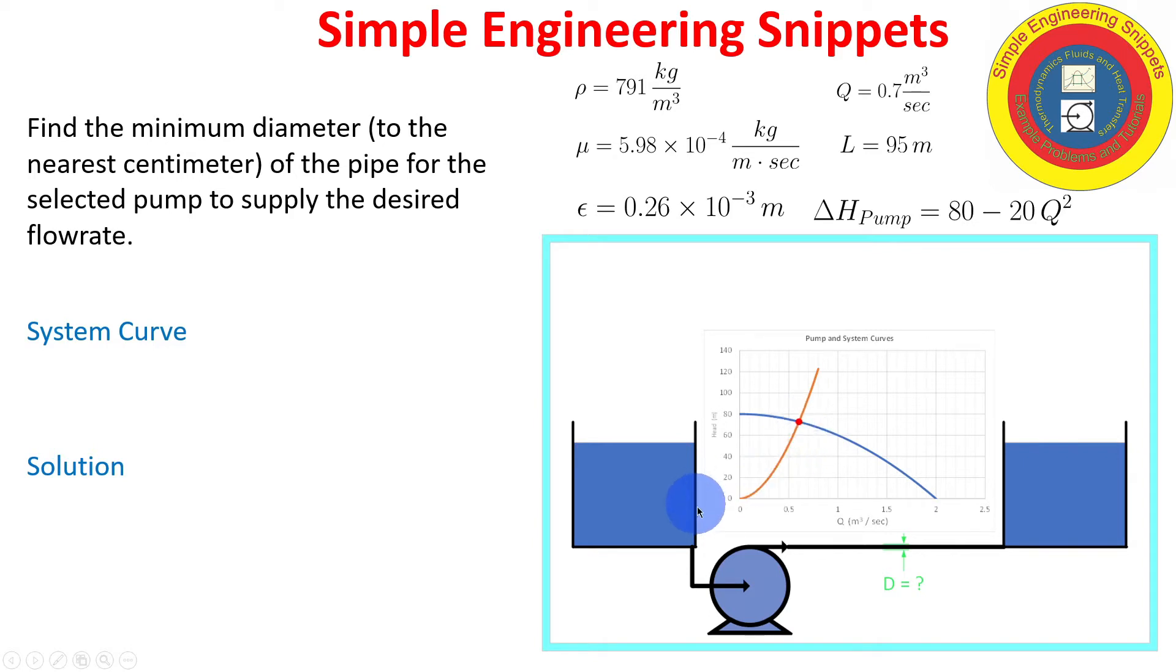In this case, it looks like it's right above 0.6 cubic meters per second, right at 0.6 cubic meters per second. And our desired flow rate is at 0.7, which is indicated here with the green diamond. So whatever diameter of pipe that resulted in this system curve, it is too small. The head loss is too high. We are not getting our desired flow rate.